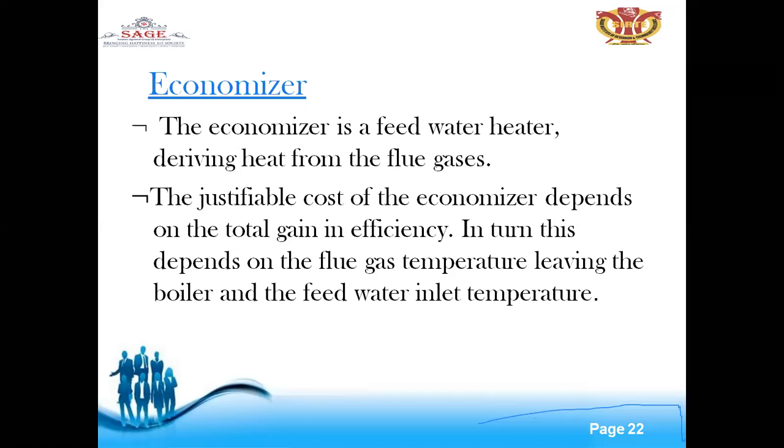The justifiable cost of the economizer depends on the total gain in the efficiency. In turn, this depends on the flue gases temperature leaving the boiler and the feed water inlet temperature.